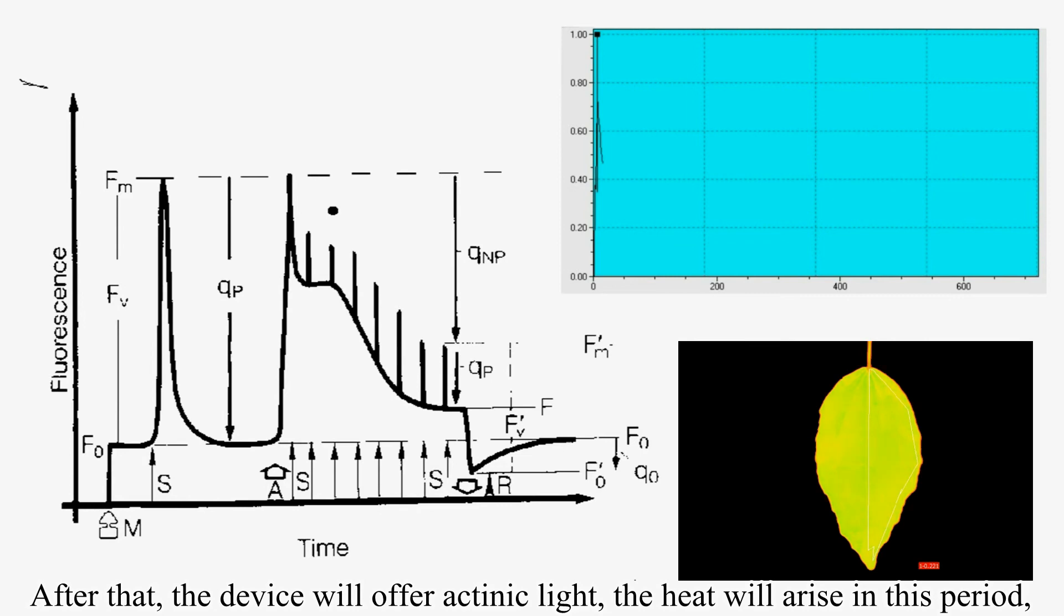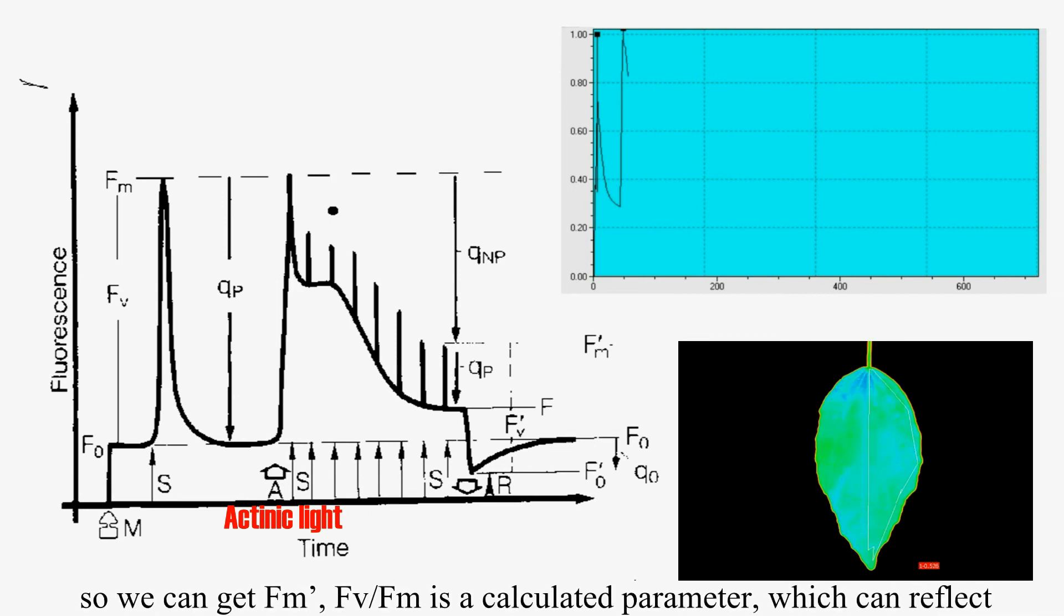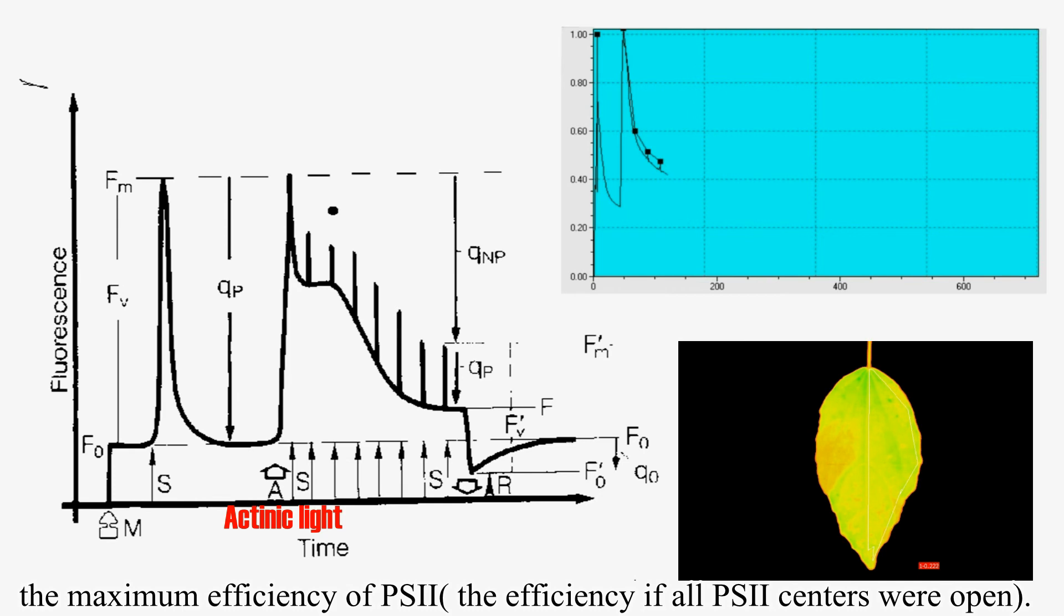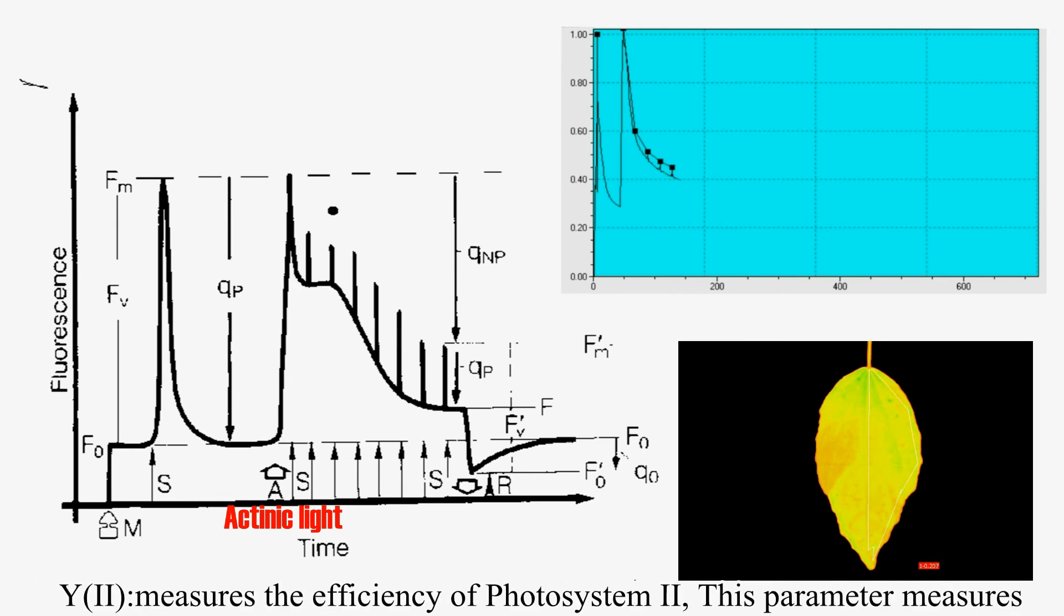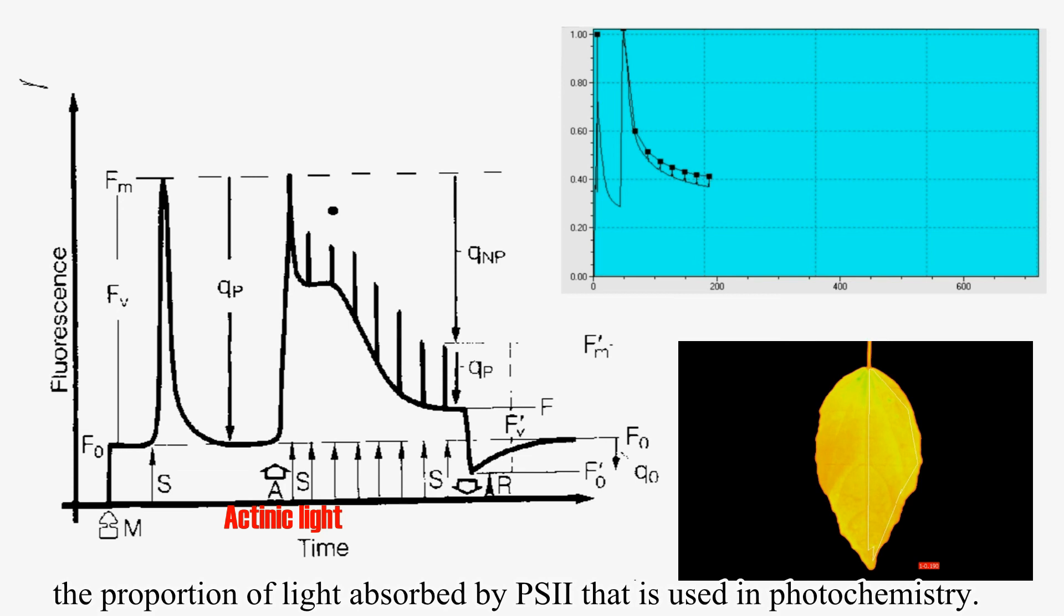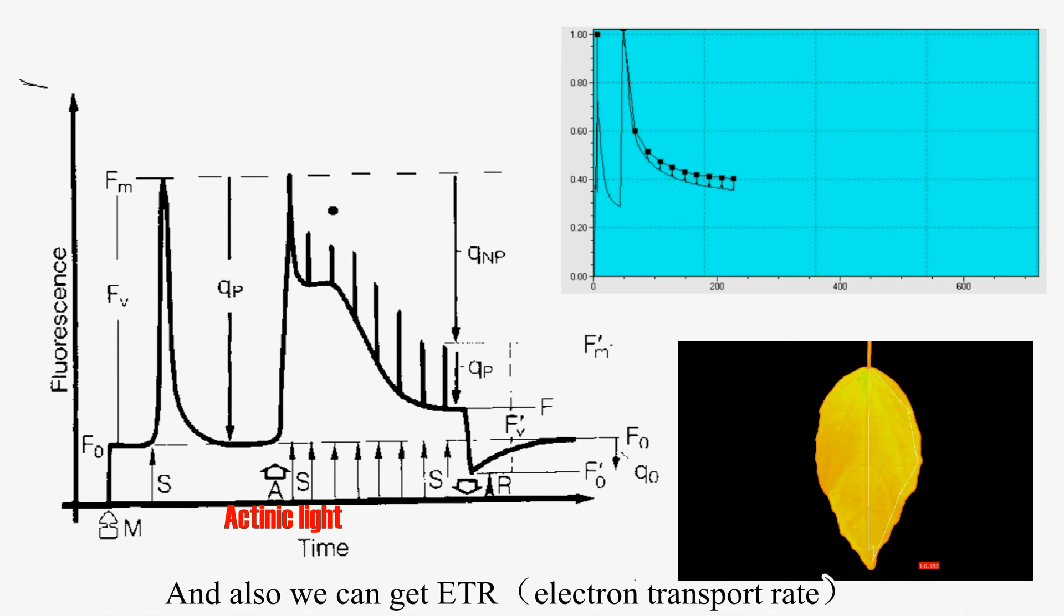After that, the device will offer actinic light. The heat will arise in this period. So we can get maximum fluorescence under light. FV/FM is a calculated parameter which can reflect the maximum efficiency of PSII. Yield of PSII measures the efficiency of photosystem 2. This parameter measures the proportion of light absorbed by PSII that is used in photochemistry. And also, we can get electron transport rate and non-photochemical quenching and so on.